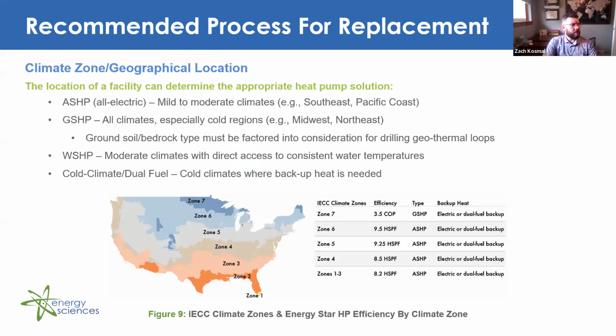So first is your climate zone or geographical location. The location of a facility can determine the appropriate heat pump solution. So an air source heat pump or all electric air source heat pump is typically used in mild to moderate climates, the Southeast, Pacific Coast, etc. Ground source heat pumps, as previously mentioned, typically work in all climates, especially cold regions like the Midwest and the Northeast. And as I mentioned, ground soil or bedrock type must be factored into the consideration.